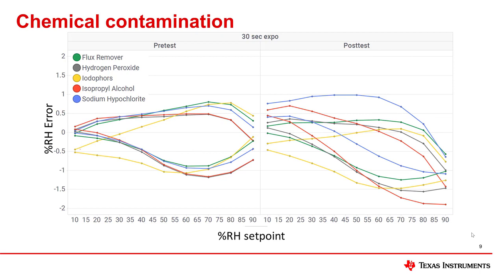The following graph shows the shift in the percent relative humidity error of a humidity sensor after exposure to certain chemicals. For this testing, five drops of each chemical were dropped directly on the sensor opening. The post-test results show a small negative gain that was introduced after chemical exposure.